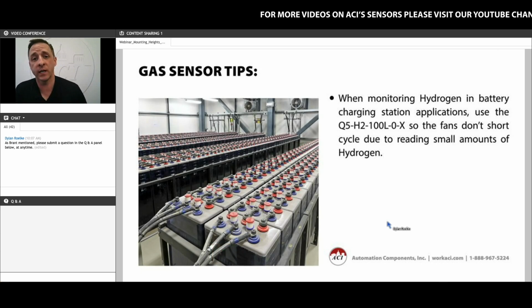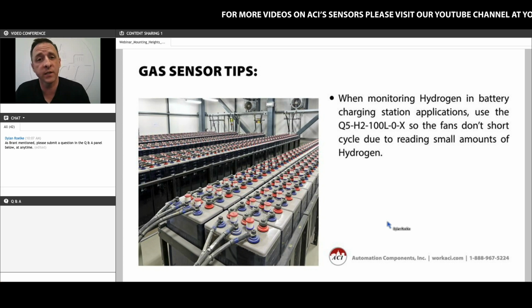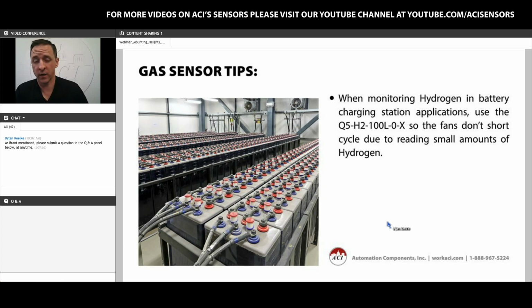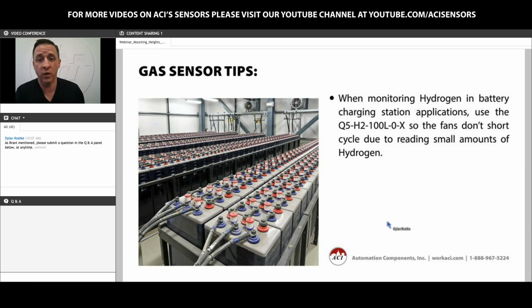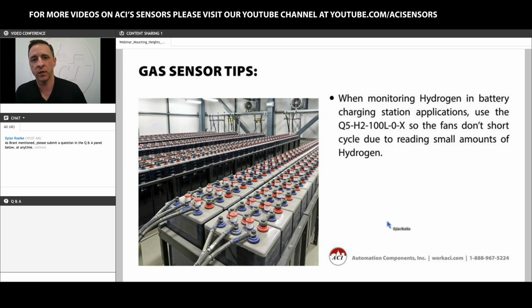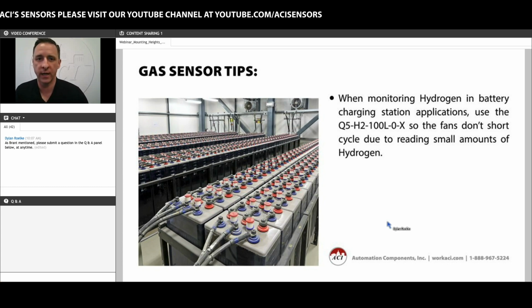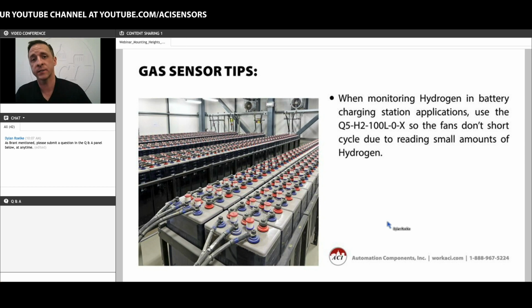An application that we're seeing more and more regularly in recent years is the use of hydrogen sensors in battery charging areas, or for things like server backups, golf carts, and electric cars, because these are typically wet cell or lead acid type batteries, and they give off hydrogen as part of the chemical reaction that occurs when the batteries are charging. In these applications, the hydrogen is lighter than ambient air and will rise to the ceiling, and if the levels build up enough, it could be potentially combustible.